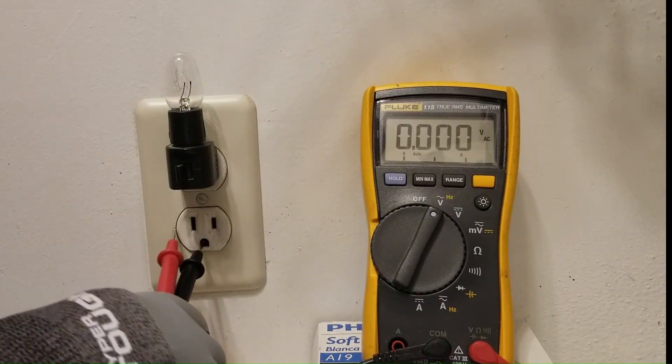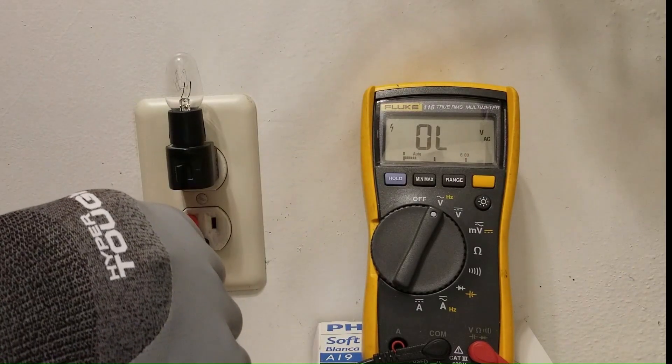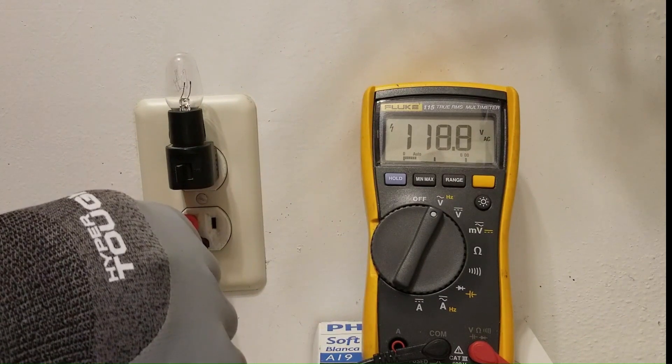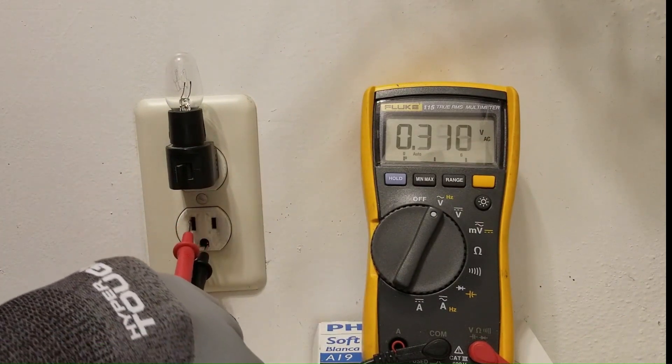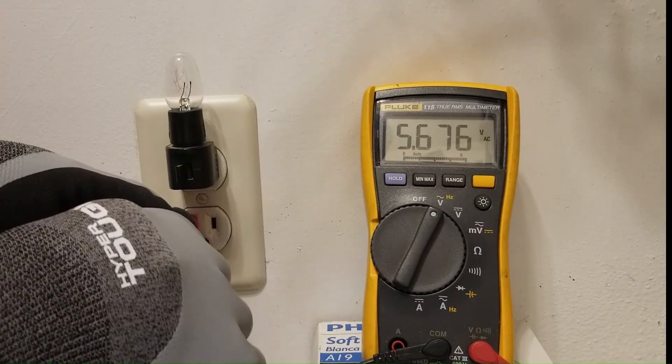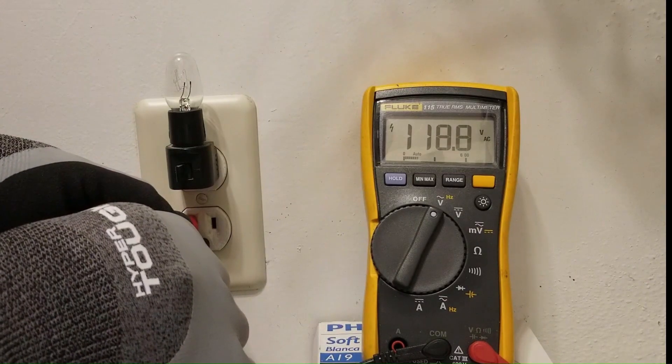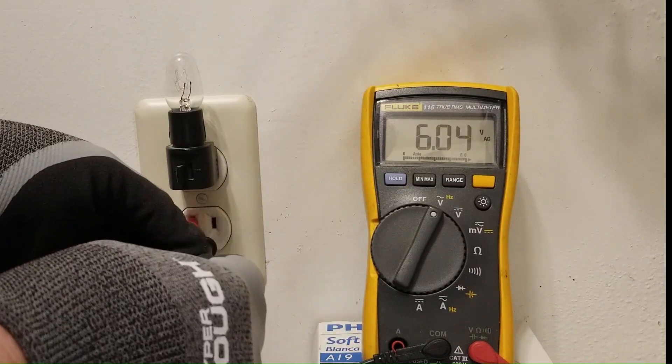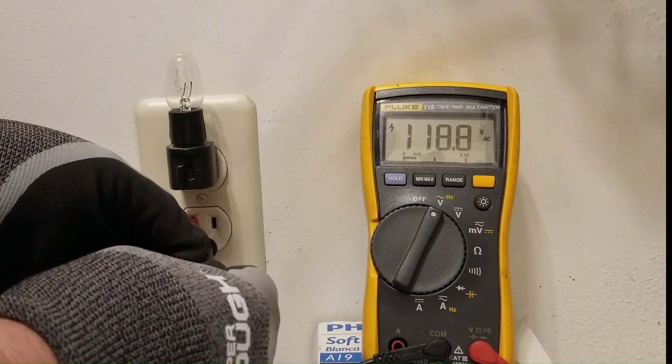So what we can do is we can put one lead into ground and one lead into neutral and it's showing 118 volts. So neutral is obviously way above the ground level, should not be up there. So that tells us we have a loose neutral right there. Neutral's reading 118 volts.